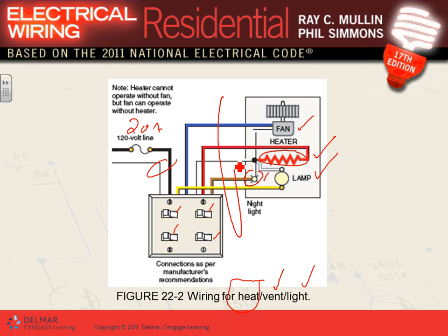Now, how many conductors are going to be taken to this fixture? You have 1, 2, 3, 4, 5 conductors to this fixture. Do we have a 5-conductor NM cable? No. So how are you going to wire it? Right? You can't do it with the NM cable. So you're going to end up with flexible metallic conduit, some type of flexible metallic conduit, and you pull 5 conductors inside that flexible metallic conduit. So that will change the way we wire.